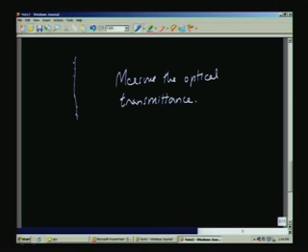I will just give them in some detail. For example, you have the dust particles or the soot particles have been collected on the filter element. We can compare this visually with a sample of known density of particles deposited on another filter paper, which can be taken as a reference.